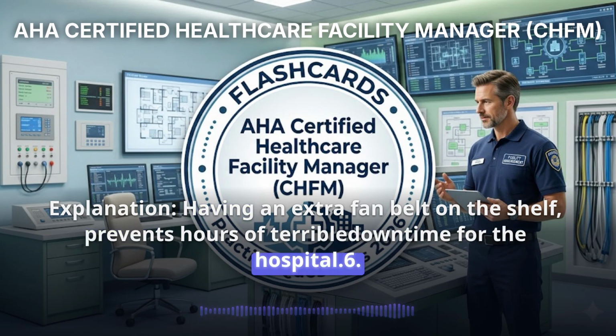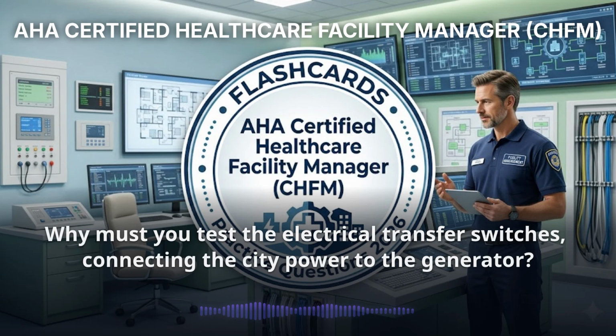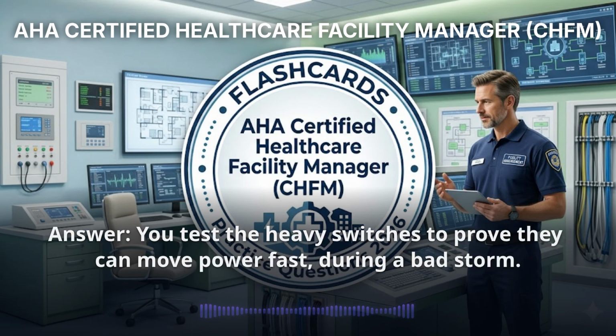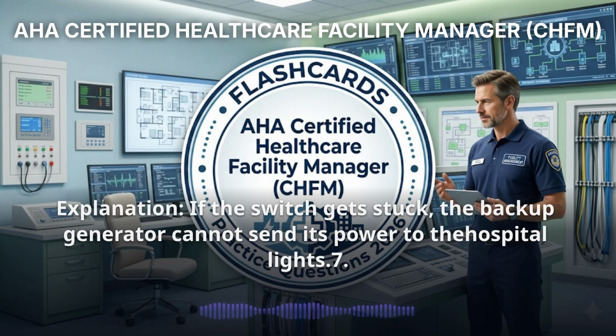Point 6. Why must you test the electrical transfer switches connecting the city power to the generator? You test the heavy switches to prove they can move power fast during a bad storm. If the switch gets stuck, the backup generator cannot send its power to the hospital lights.